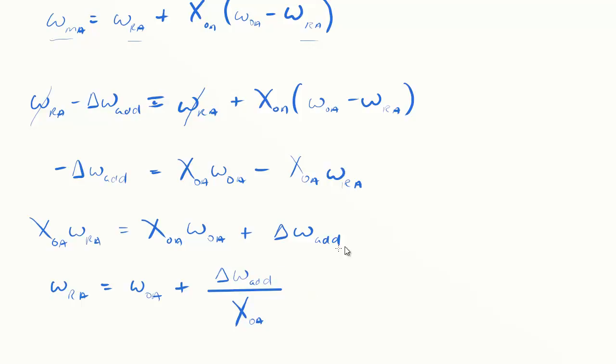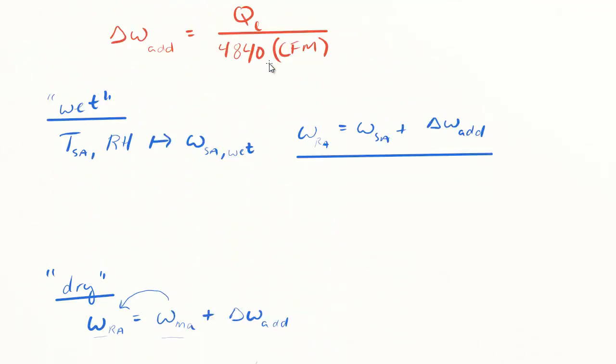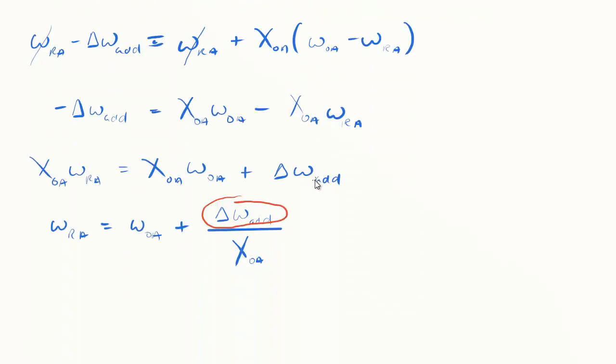Divide both sides by X_OA and we get our final formula for the return air absolute humidity ratio. That X_OA cancels, I get just the outside air plus the omega added in the space divided by that outside air fraction.